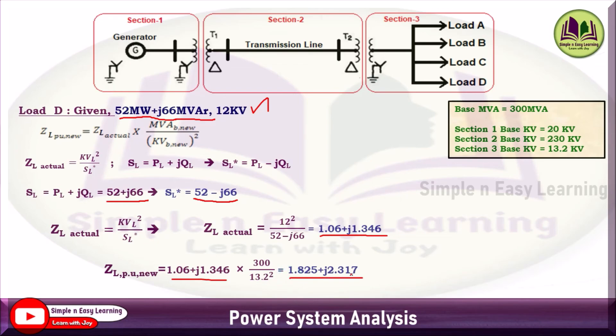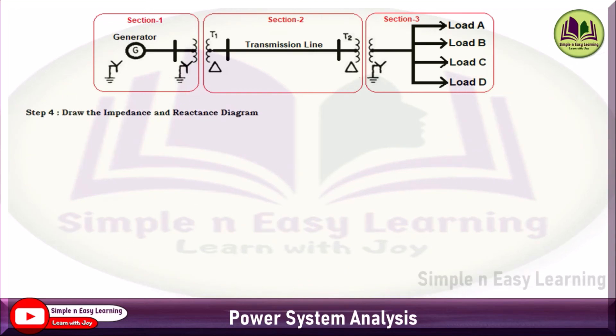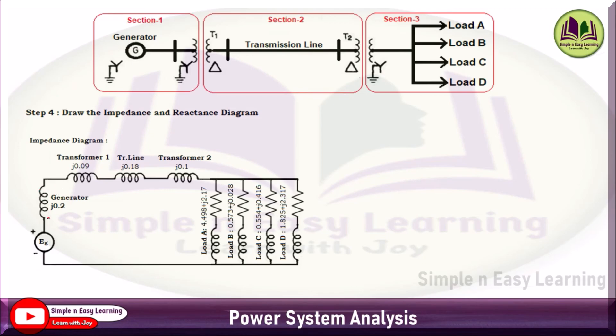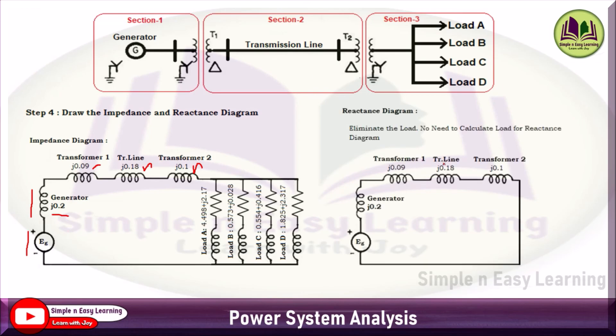Step 4: Draw the impedance and reactance diagram. For the impedance diagram, draw the generator with EMF and j0.2 pu, followed in series by Transformer 1 (j0.09), transmission line (j0.18), and Transformer 2 (j0.1). Then four loads — A, B, C, D — are connected in parallel, each with resistance and reactance. For the reactance diagram, simply eliminate the loads and represent only the generator, Transformer 1, transmission line, and Transformer 2.